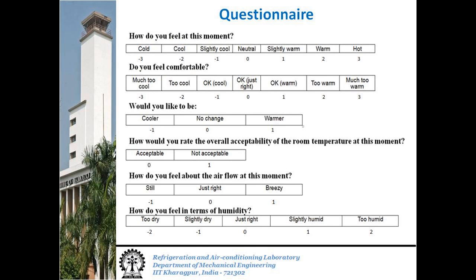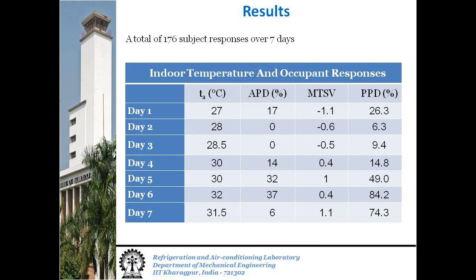Numbers put below the options are the numerical values that were used for later analysis. These numbers were not put in the actual questions though. A summary of some of our observations is given here. One important thing to notice is the large differences between APD and PPD values. APD is the actual percentage of dissatisfaction among occupants as calculated from their survey responses, while PPD is the predicted percentage as calculated from Fanger's model.